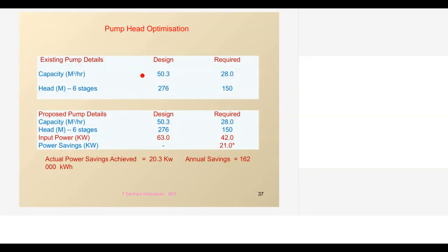So here, based on the measurement and other details, the audit recommended that at least one stage in this pump can be provided with a blind. When we say blind, there is no impeller, it is only a steel disc. Then where to put the blind? You can't put it on your own choice. Whenever a blind has to be provided, we have to consult the pump supplier. He will tell whether you can remove the second stage or third stage, then you provide a blind for that. With all these things, we estimated that earlier it was taking 63 kilowatt. Once they reduce one stage with a blind, it can take 42 kilowatt. So the power saving estimated was 21 kilowatt. The actual saving achieved was 20.3.